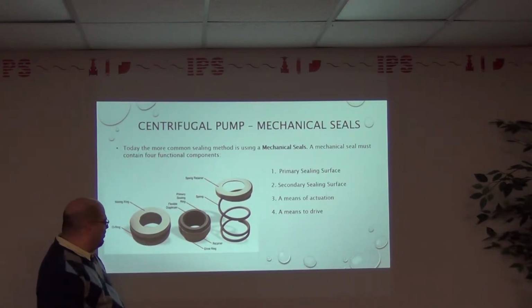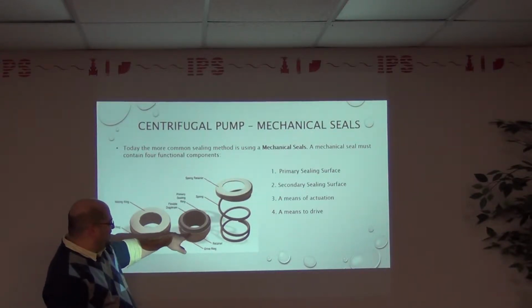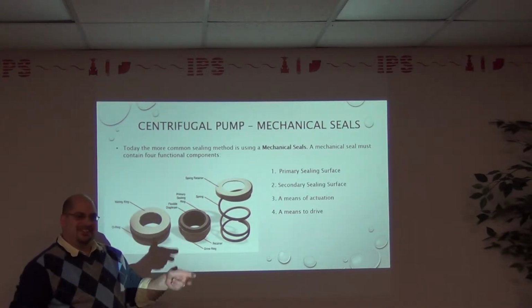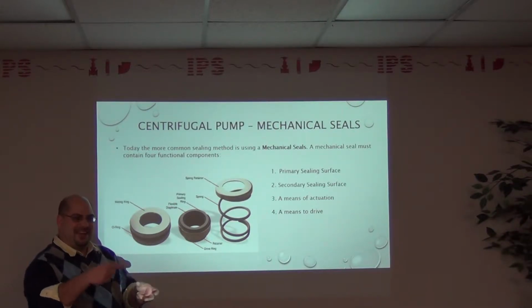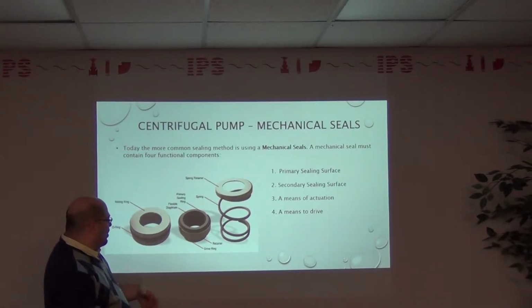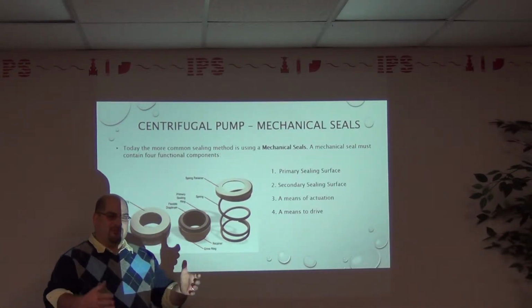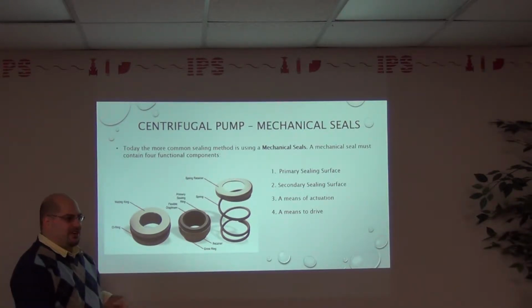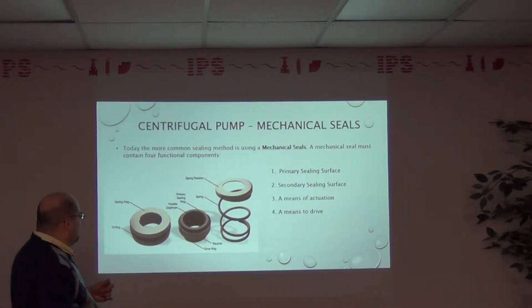Years ago, when I first came into this industry, you would take the mechanical seal, flip it around, polish that side, and reuse the seal. Now these guys got smart. Now they cut a divot on the back end of the seal. Or also, we used to lap it. We used to get a marble block and repolish those, and it was a skill unto itself. That's gone. I don't know anyone who relaps mechanical seals, but that's what people were doing when I started.